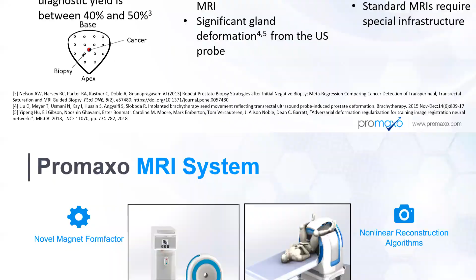The Promaxo MRI system is an open, single-sided 0.066 Tesla MRI machine. The system consists of a magnet cart and an electronics rack, as shown in the image on the left. The rectangular electronics rack houses the electrical components of the system. The magnet cart houses the magnet, gradient coils, and transmission coil, and attaches to the rigid external pelvic receive coil, which is worn by the patient during the procedure. For prostate cancer imaging, the patient is in a lithotomy position with their legs around the magnet cart, as shown on the image on the right. The imaging field of view is 6 inches from the face of the magnet and has a diameter of 4 inches.